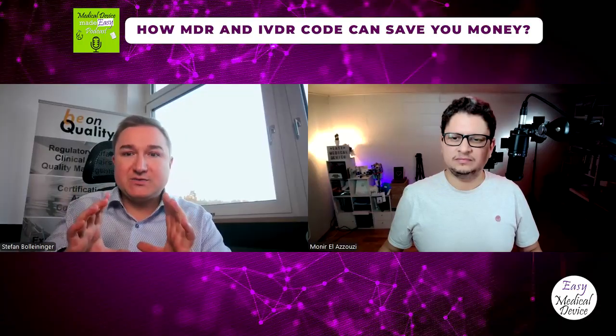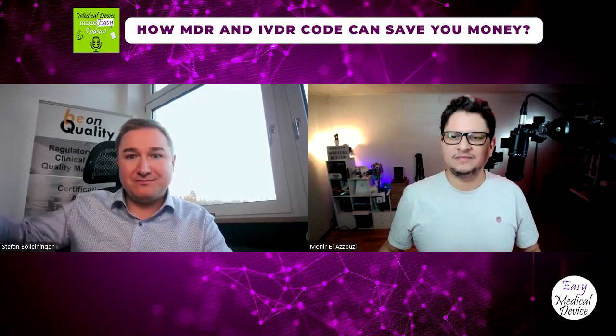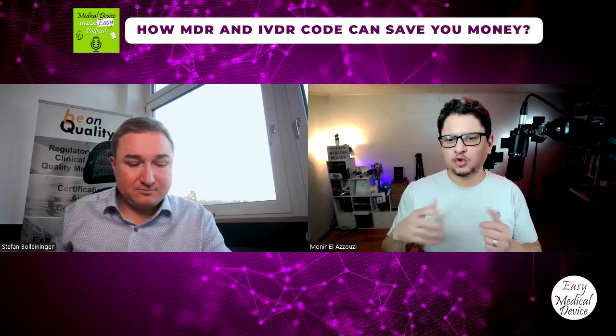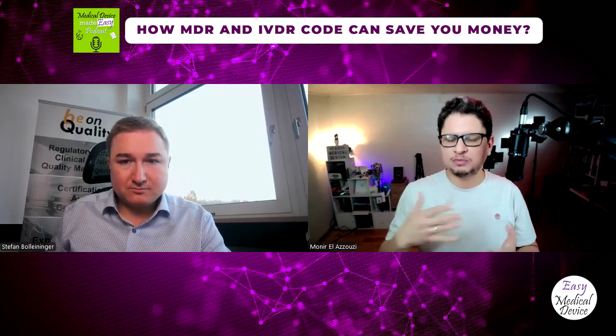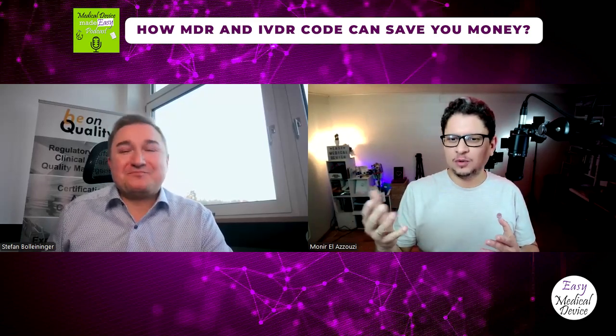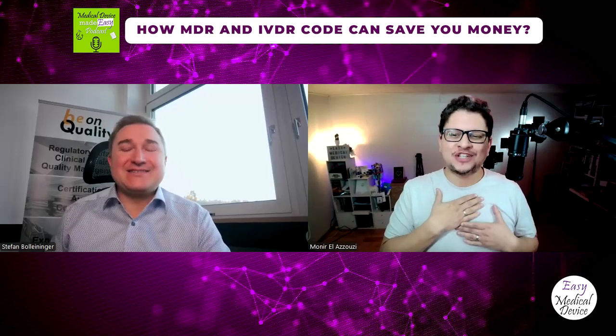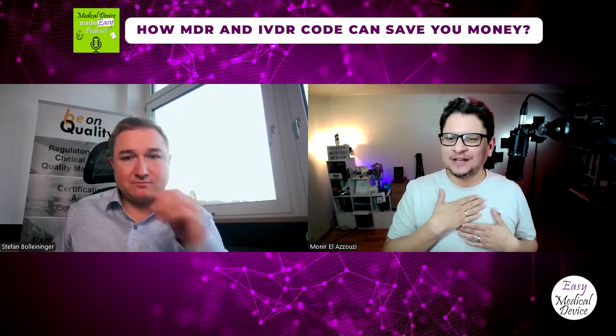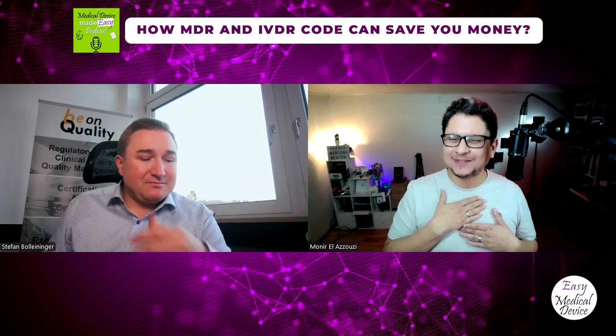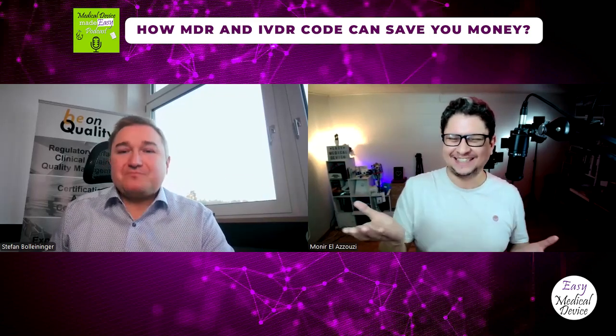on that. And then also per certificate validity, per, in this case, generic device group, one product for the 5 years. And so that's how you can play with that. And that's what you need to do by initial certification. You play with the smallest product because then you have 5 years for the big one. Exactly. And you can also try to imagine which product would be selected afterwards. I mean, I had the chance sometime that the notified body asks me which one you want me to check, and then I give it.